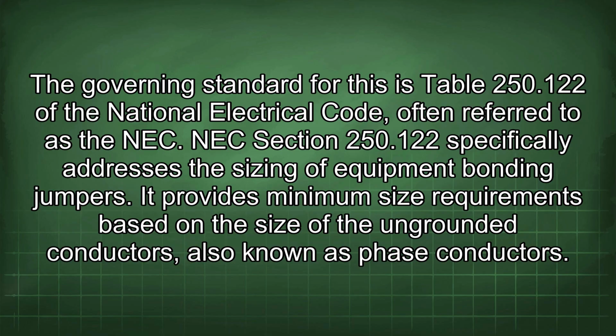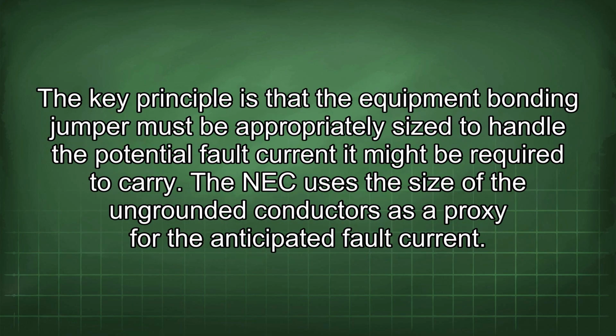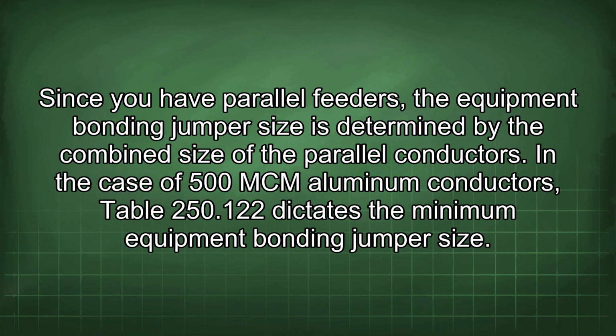NEC Section 250.122 specifically addresses the sizing of equipment bonding jumpers. It provides minimum size requirements based on the size of the ungrounded conductors, also known as phase conductors. The key principle is that the equipment bonding jumper must be appropriately sized to handle the potential fault current it might be required to carry. The NEC uses the size of the ungrounded conductors as a proxy for the anticipated fault current. Since you have parallel feeders, the equipment bonding jumper size is determined by the combined size of the parallel conductors.